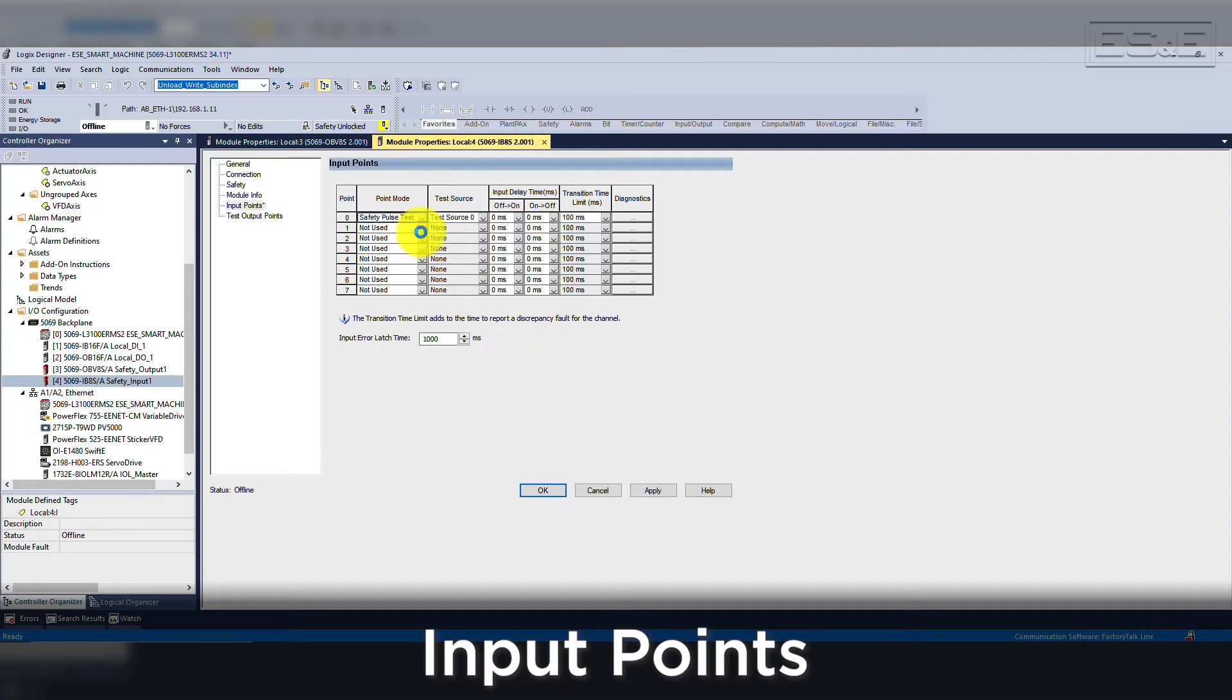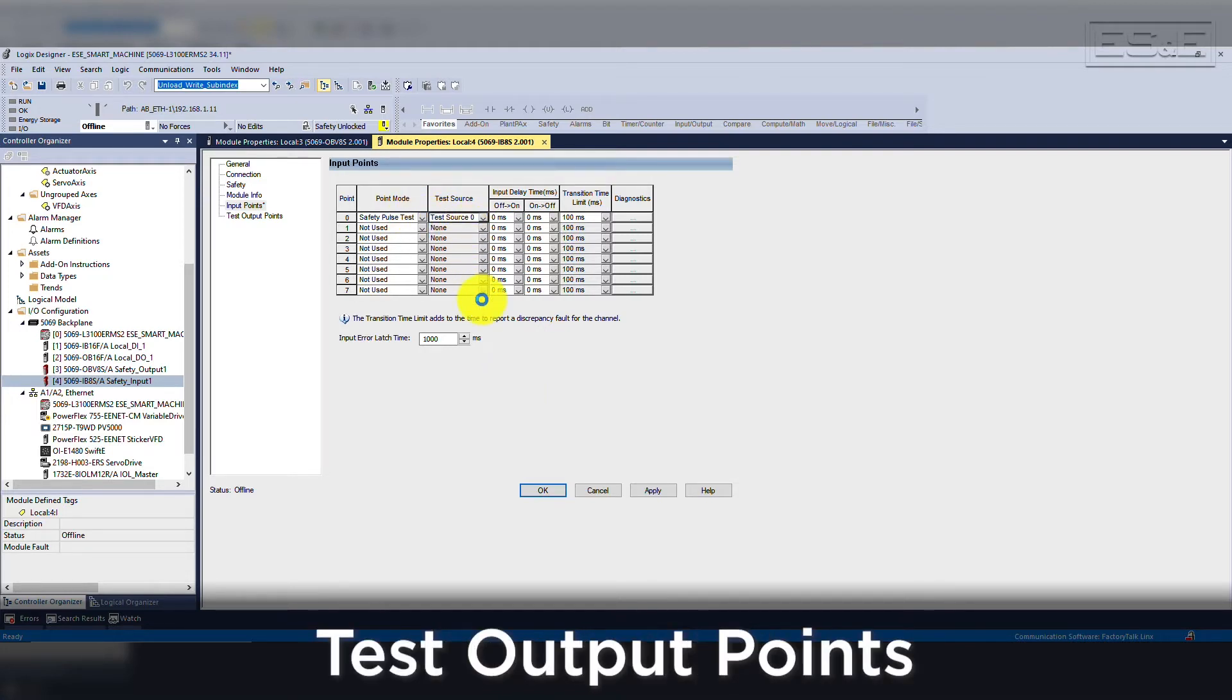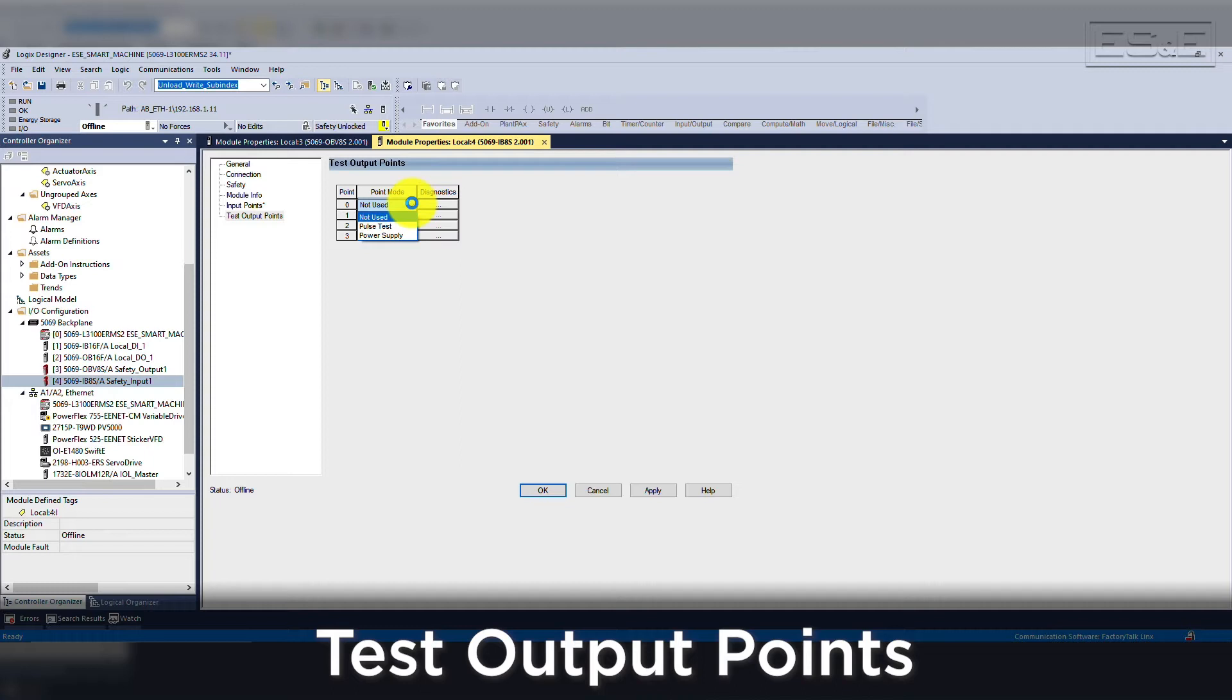If you select safety with pulse test, you will then need to assign the test source. Test sources are configured on the test outputs and can be set up with pulse test or power supply. Power supply can be utilized to feed power to an OSSD device, but you should review the power requirements to ensure that you have enough power for the device without overloading the card.